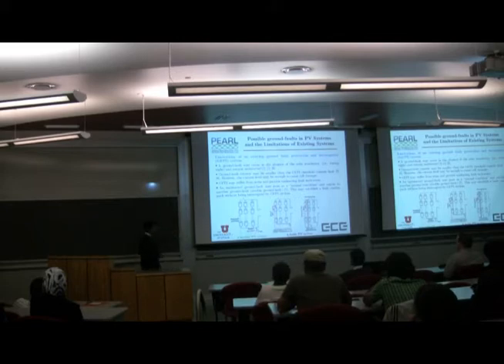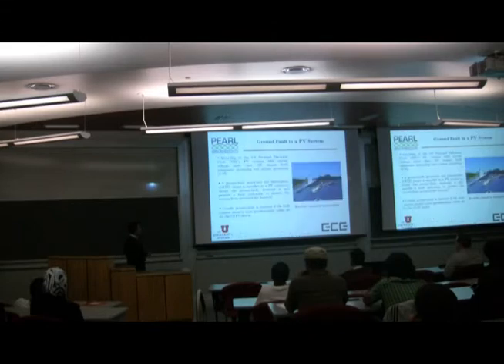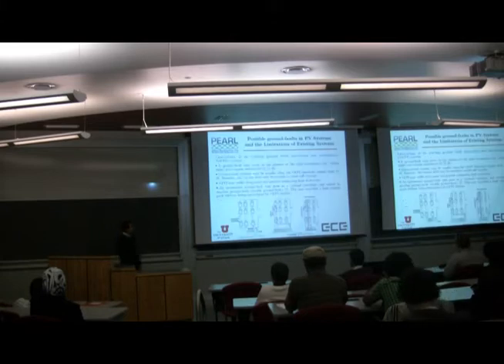The question is, these two lines are separate, but how could there be a short circuit in between? Say there's a crack in the solar panel and water gets into this crack, and it would actually create a short circuit between the chassis ground and the system ground. It is very unlikely that there would be a crack and water gets into the system, because the solar panel would keep working, but there would be a short circuit between these two terminals.